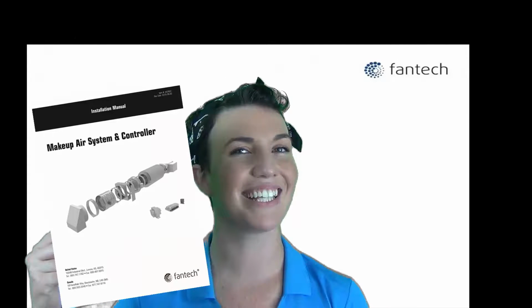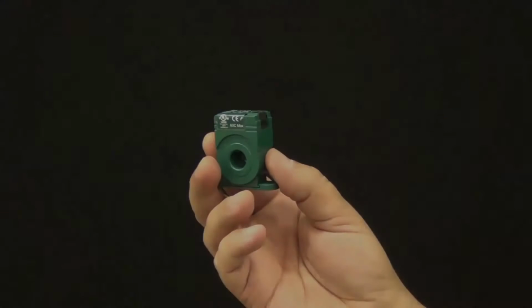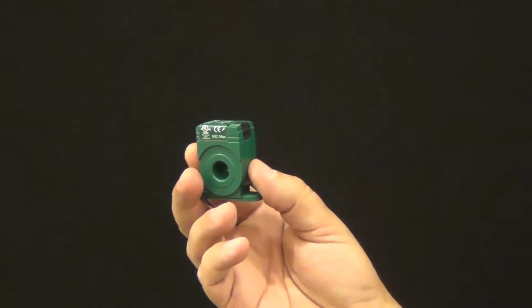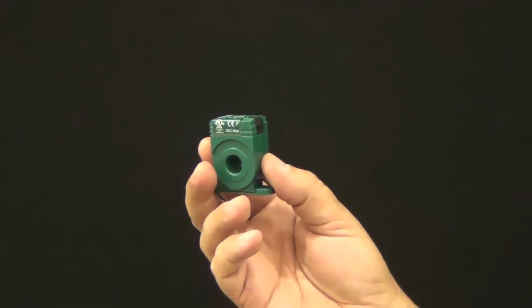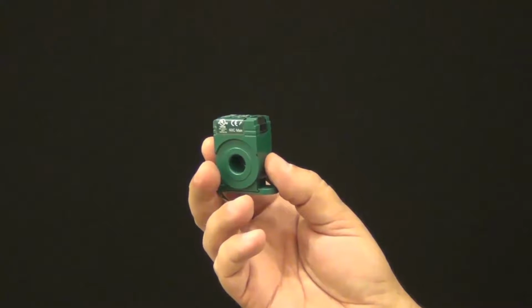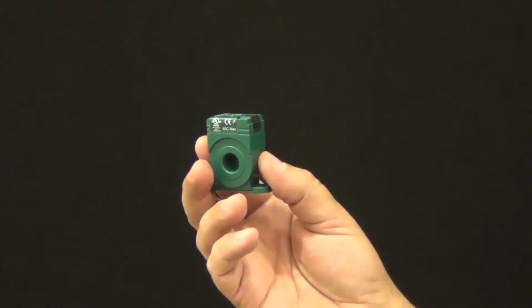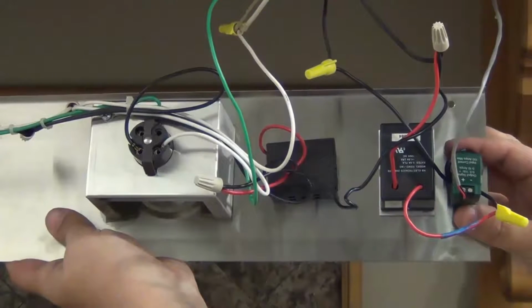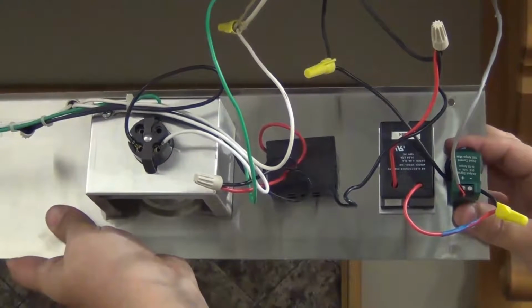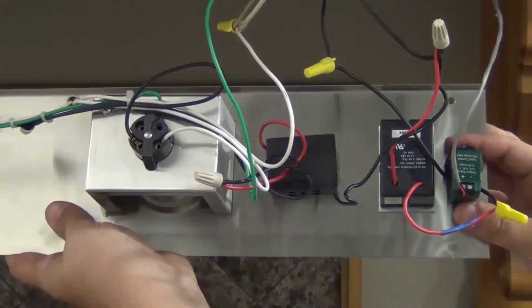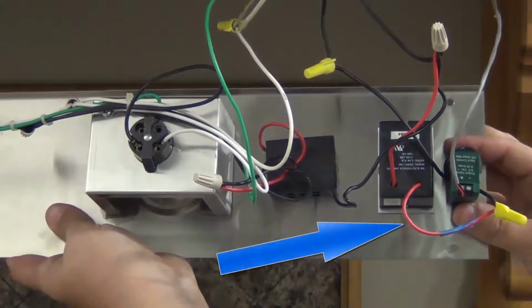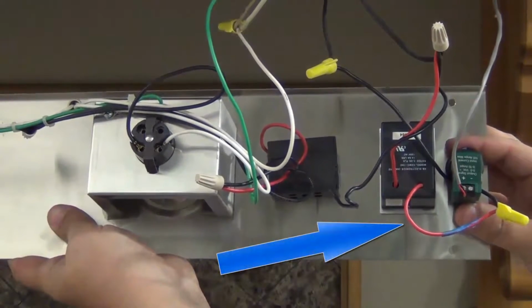The instructions for wiring, commissioning, and operations of the Fantech Makeup Air system are in the installation manual. For the purposes of demonstration and explanation, here we show the mounting of the included current transducer on the electrical plate of a range hood liner. The load leg of the exhaust fan speed control is installed into the transducer.